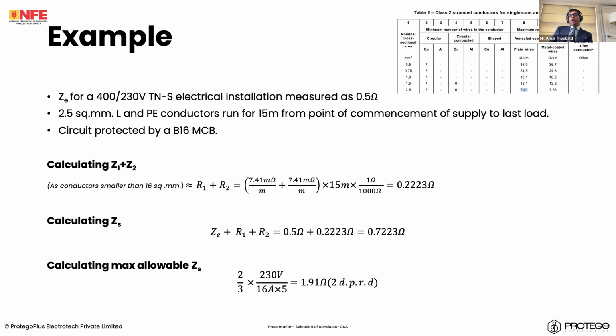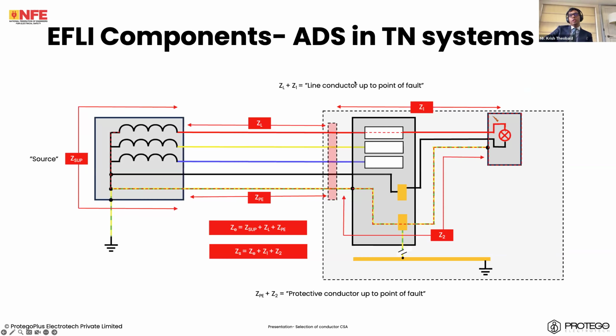How do we ensure that this value is not exceeded? Remember, we measure earth fault loop impedance as a part of verification. However, it's not okay to just erect the installation and then say, oh my God, I should have selected a bigger cable. This has to be calculated at the design stage.